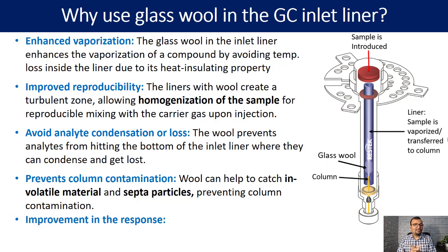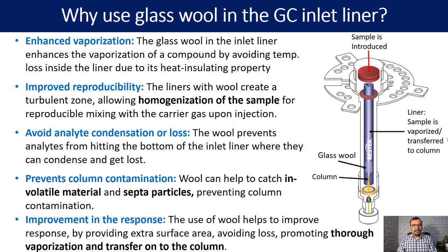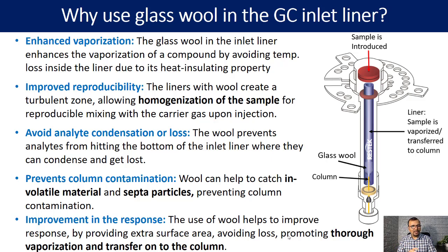Similarly, the glass wool can also help to achieve improved response for your analyte. The use of wool helps to improve response by providing extra surface area and avoiding the loss of analyte. This promotes thorough vaporization and transfer onto the analytical column, which eventually results in improved response for your analyte.